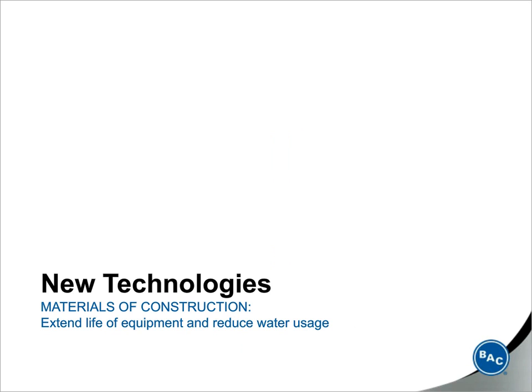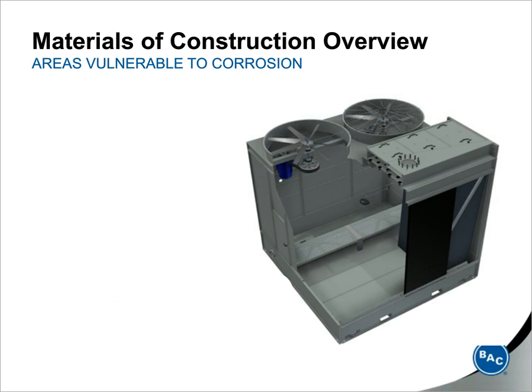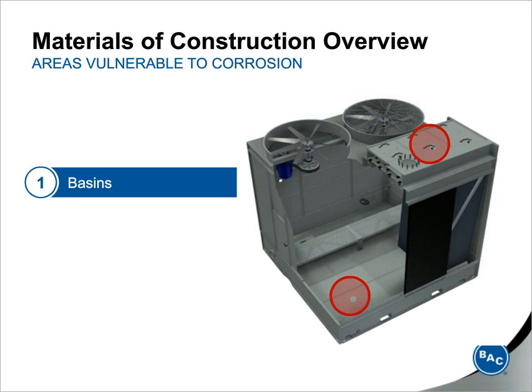So now we're going to talk about one final new technology, which is more advanced materials of construction that can extend equipment life and reduce lifetime water usage. There are really three main areas of the unit that are most susceptible to accelerated corrosion. So these components are your basins. The basins on top of the unit are your distribution basins. The basin at the bottom of the unit, that's your cold water collection basin.